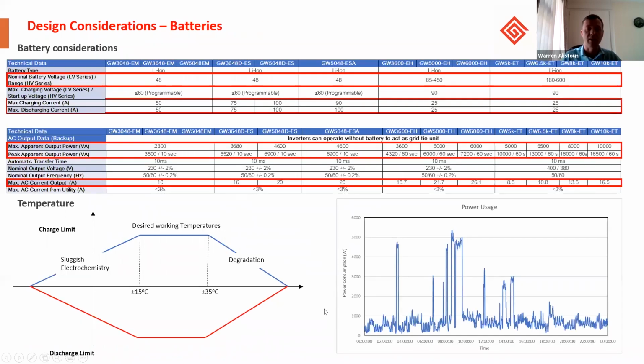Okay. Moving along to the battery considerations. First of all, again, through the product range, the low voltage series, we work with 48-volt batteries. The high voltage series on the single phase, 85 volts to 450 volts. And on the three-phase series, 180 volts to 600 volts. Another very important aspect is the charge and discharge current for each product family. For the EM, we see 50 amps is the restriction. For the 3.6 kilowatt ES, 75 amps. For the 5 kilowatt ES, 100 amps.